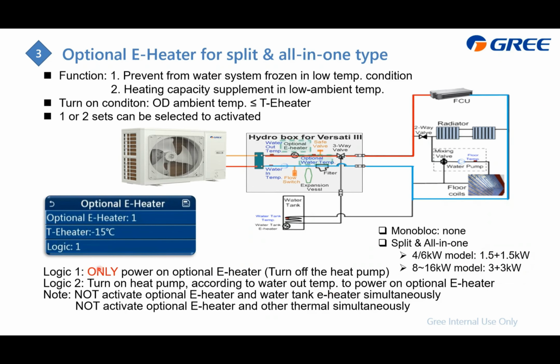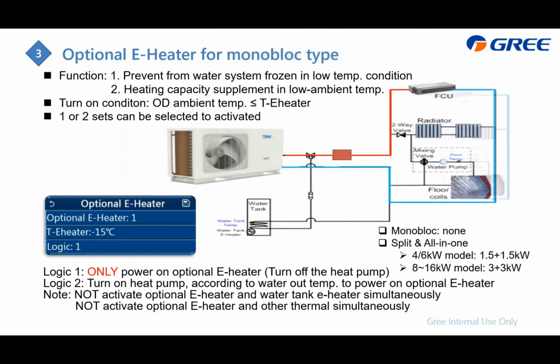As for the difference between the logic 1 and 2, it is whether you need to turn off the heat pump. Logic 1 is turned off, and logic 2 is depending on the water out temperature. This one will turn on the optional heater, also acting as a supplement. And this slide displays the optional heater for monoblock. It should be located at this location, which means this is only for the heating, not for DHW.